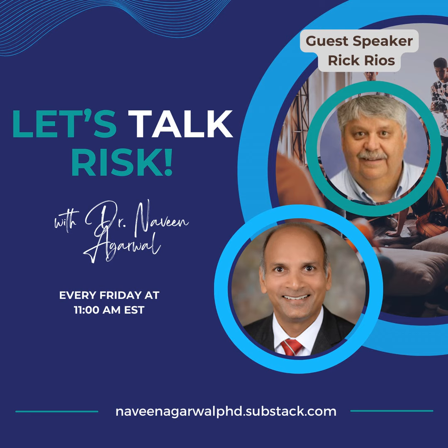If it's not, a lot of times, to be honest with you, there's stuff on the IFU that may not be in the risk management file. And so now you start questioning, why is it a caution and warning if the risk management doesn't have it, right? Yeah, for sure. And so it becomes an issue from that standpoint. So we look at the labeling and we look at the IFU and we look at risk through that lens. And so there are different lenses.